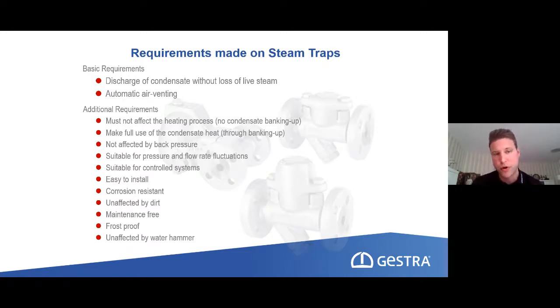And the second very important requirement we have here is the automatic air venting. As soon as I shut down a system and it is not pressurized anymore, air has the possibility to enter the system. And if that happens, the air will remain in the system as long as I didn't bring it out. So I have to bring it out of the system to have a very good heat transfer rate, because air prevents the heat transfer, and it does it very well. If you think of your radiators at home to heat up your living room, if you have air in your radiation system, then you will have a very cold surface, and that is not the right functionality for your radiator. So we have to get it out.